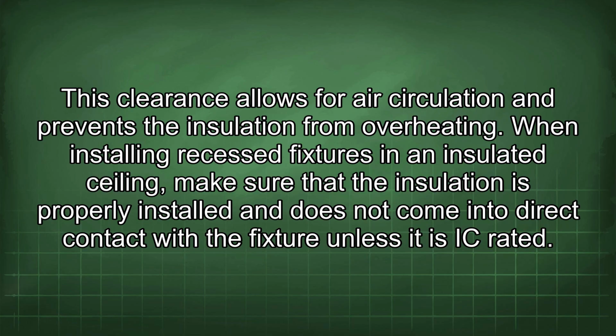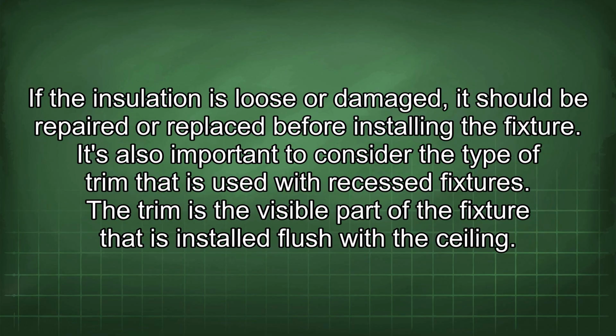When installing recessed fixtures in an insulated ceiling, make sure that the insulation is properly installed and does not come into direct contact with the fixture unless it is IC rated. If the insulation is loose or damaged, it should be repaired or replaced before installing the fixture.